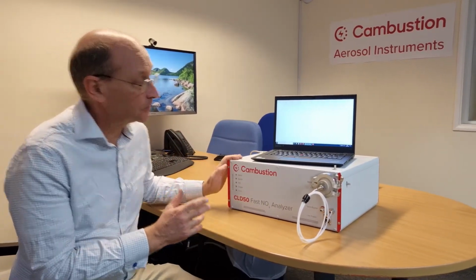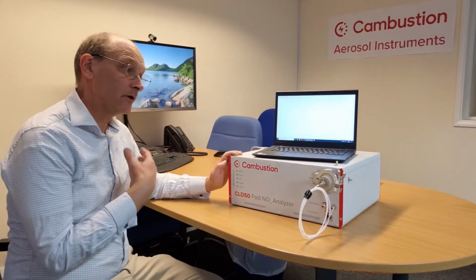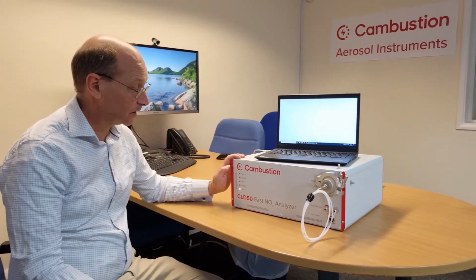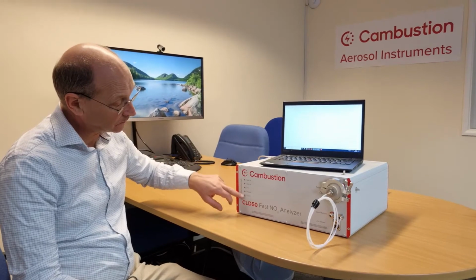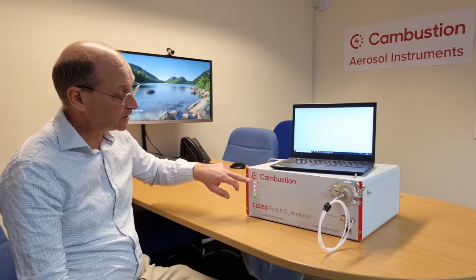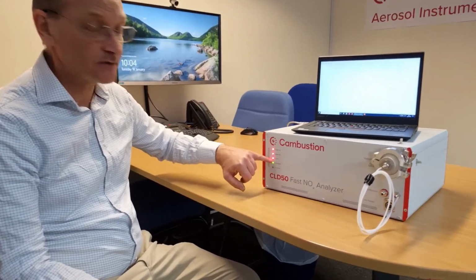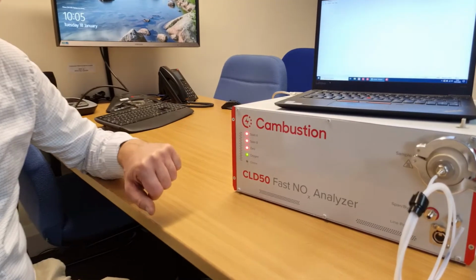So we've got the equipment connected up now. Now it's time to switch on and start warming the analyzer up. The first thing I'm going to do is switch on the power on the rear panel, and you'll hear a cooling fan start, but you'll also see the LEDs on the front panel indicating which gases are connected. So we've got our oxygen connected. I haven't connected any of the calibration gases, so they are indicated as red.